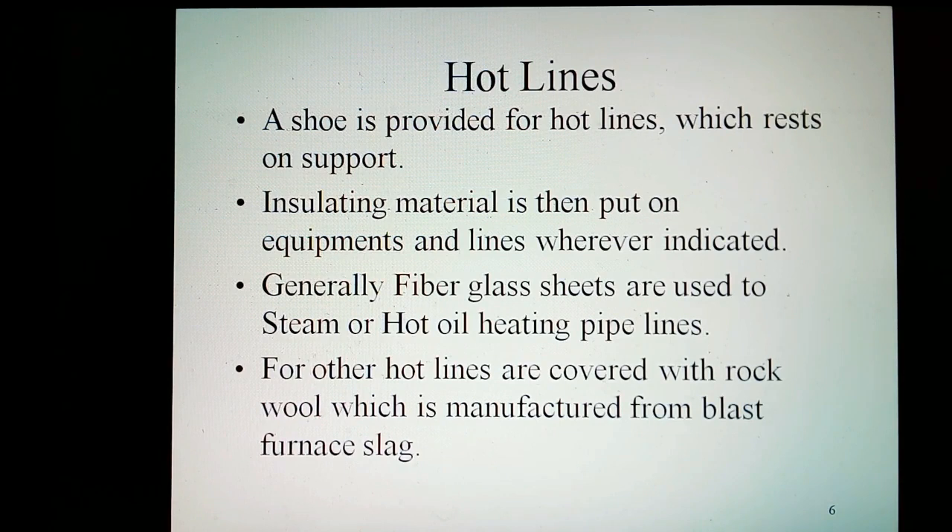Insulating material is then put on equipment and lines wherever indicated. Generally fiberglass sheets are used for steam or hot oil heating pipelines. Other hot lines are covered with rock wool, which is manufactured from blast furnace slag.